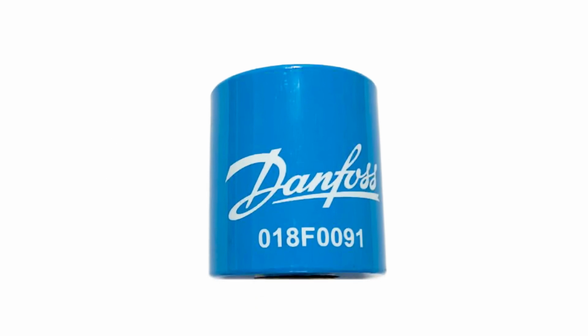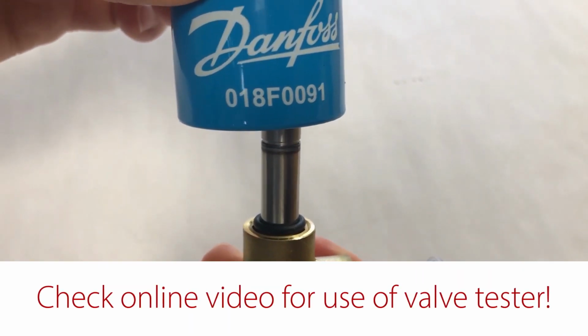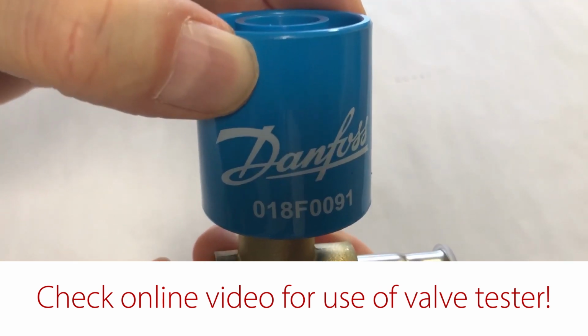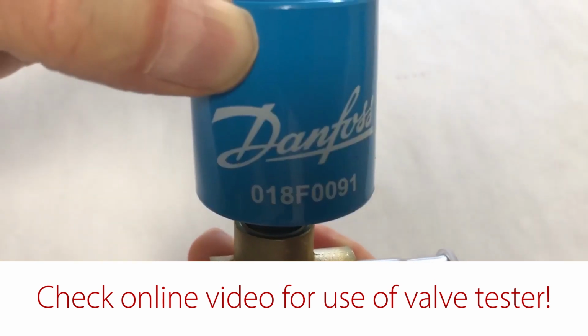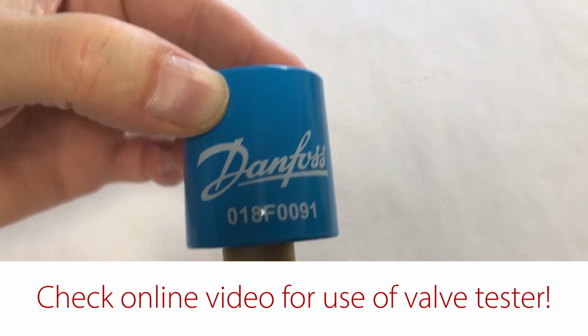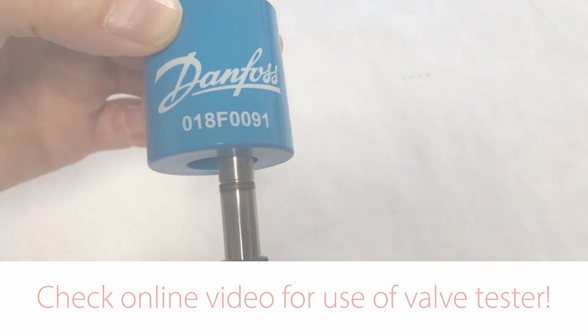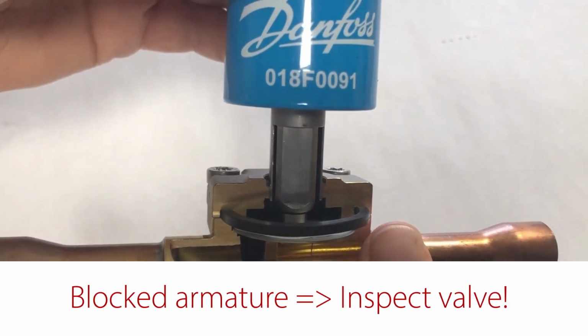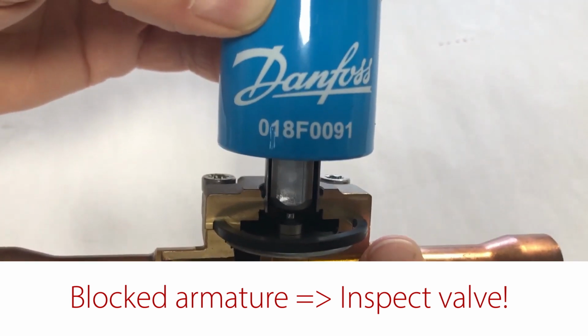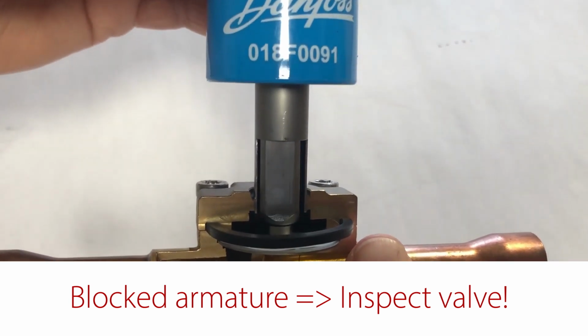This is done by using the Danfoss magnetic valve tester, code number 018F0091, which is available from the Danfoss product store. Here you can see how to use it to check the armature movement. If you can hear a click, then the armature is freely moving, otherwise it might be blocked. In this case, you then need to take the valve apart, if it is serviceable, to further inspect the valve and clean it if needed.